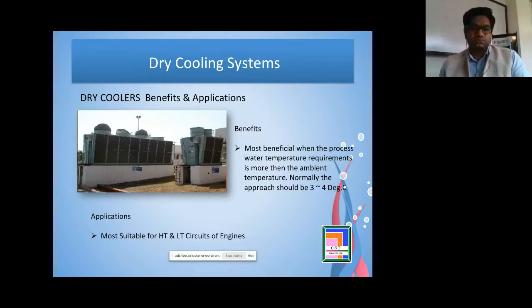Dry cooler benefit and application. The benefit is that it is most beneficial when the required process water temperature is more than the ambient temperature. Normally the approach is 3 to 4 degrees centigrade, which we already discussed in the last slides. The application is that this is most suitable for HT and LT circuits of an engine. If we have an engine, like a power plant running on diesel, HFO or gas, there are two different circuits. One is for jacket cooling, the other is the low temperature circuit, which is for charger cooling and lube oil cooling. In lube oil cooling and charger cooling, we have to go close to ambient.